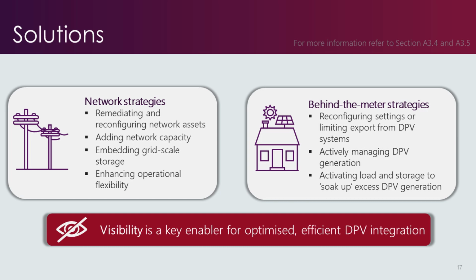patterns through the day. There are also behind-the-meter strategies which harness resources on the customer side of the meter. These include things like changing settings or limiting export from DPV systems, actively managing the DPV generation, essentially to lop off the peak to within the limits the network can accommodate, and lastly, activating other forms of DER in the low voltage network, such as load and storage devices, to soak up excess DPV generation in the daytime. Keep these in mind because the same set of solutions will have a role to play in addressing the bulk system challenges we're going to cover shortly.